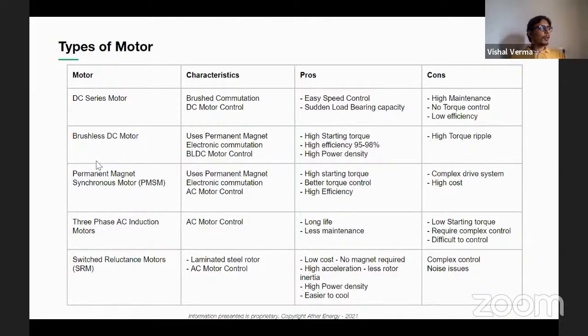So a different mechanism on BLDC control is utilized, called a permanent magnet synchronous motor. In construction, it is similar to a BLDC motor, but the control mechanism is different. Here it utilizes a sinusoidal control mechanism, which makes it high on efficiency and high on starting torque.